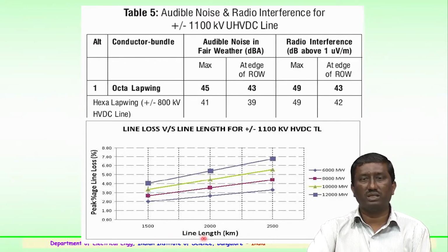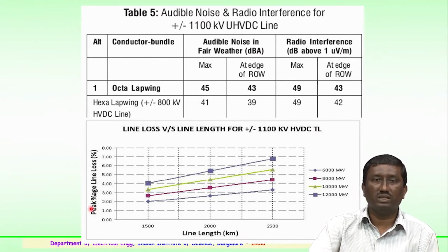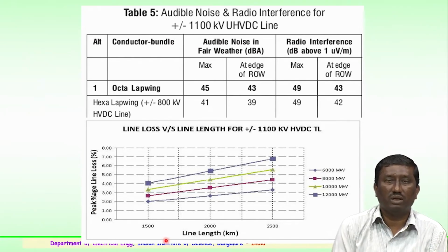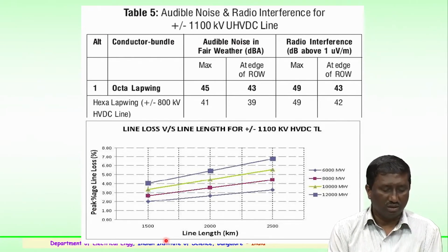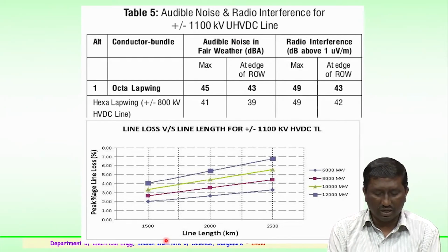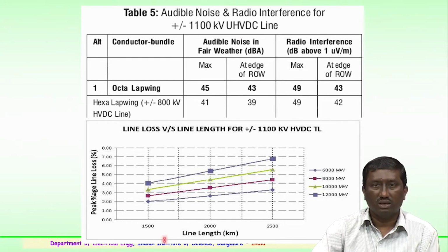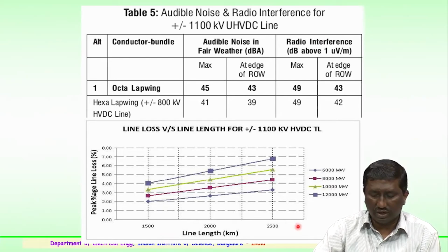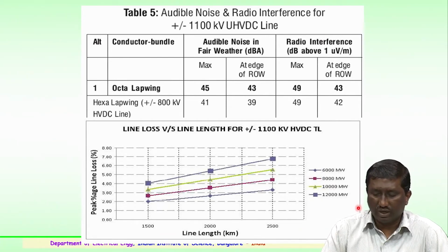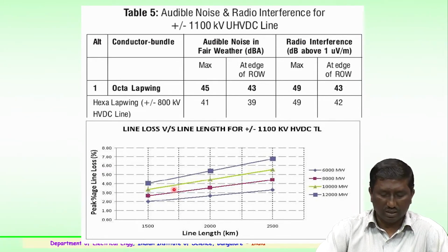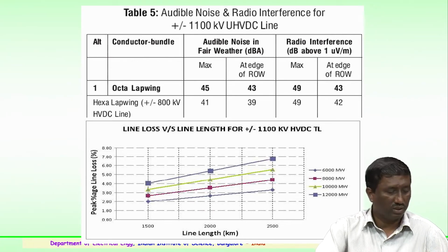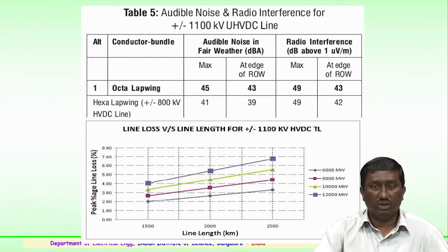As you can very clearly see, this is the line length in kilometers and this is the peak line losses in percentage. This very clearly shows, as the line length increases beyond 2500 kilometers for various power ratings, the performance of the line is shown here for 12,000 megawatts, this being 8,000 megawatts, 6,000 and 10,000 megawatts, how the line losses are seen.